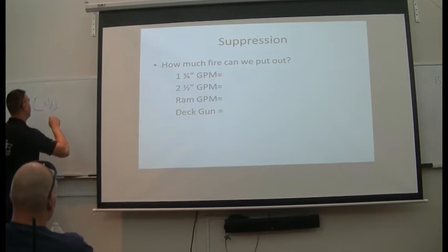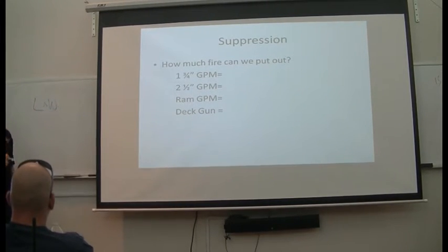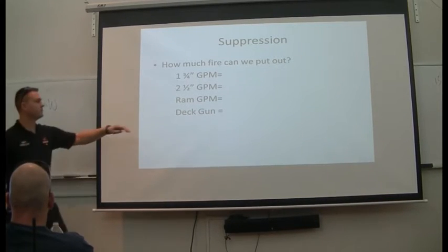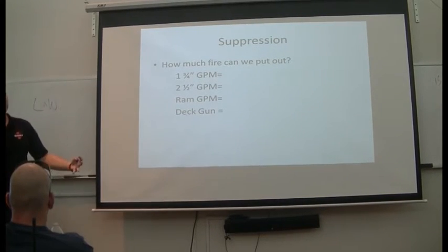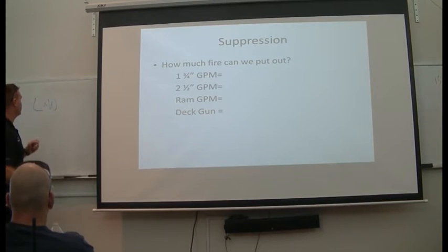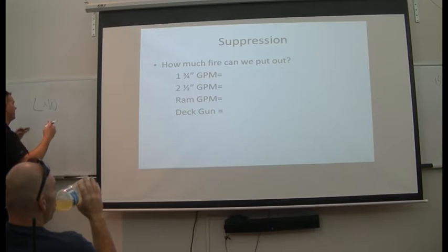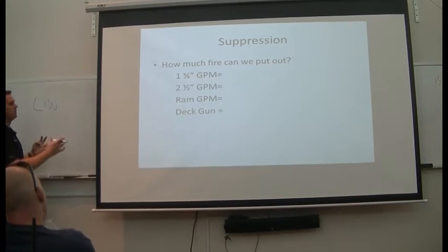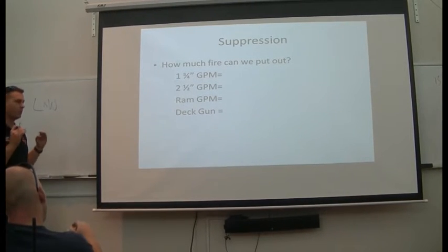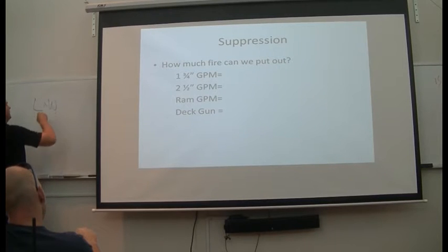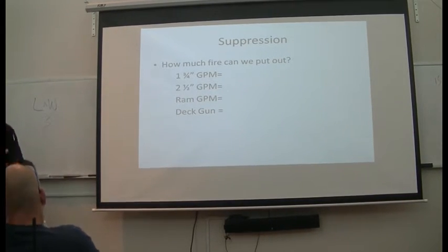So I've heard the comment a million times, I don't bring a calculator to the fire. Well, you don't need to. If you understand this and understand your capabilities, you don't need to bring a calculator to the fire. You understand, looking at a house, what size handline you need and its capabilities. If we don't do this, again, we're just guessing. We're putting wet stuff on red stuff. So length times width divided by 3. Everybody knows that equation, right? It's the NFA equation. It's right on the ITAC board.